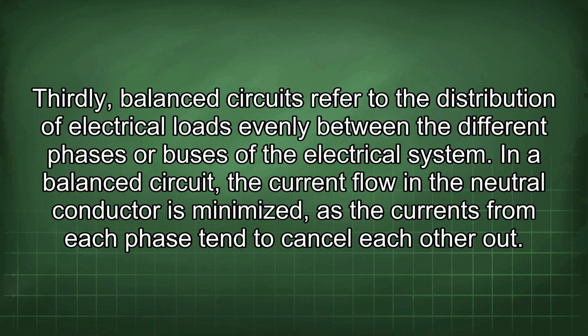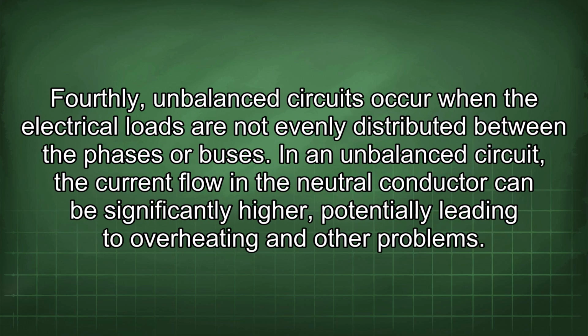Thirdly, balanced circuits refer to the distribution of electrical loads evenly between the different phases or buses of the electrical system. In a balanced circuit, the current flow in the neutral conductor is minimized, as the currents from each phase tend to cancel each other out. Fourthly, unbalanced circuits occur when the electrical loads are not evenly distributed between the phases or buses. In an unbalanced circuit, the current flow in the neutral conductor can be significantly higher, potentially leading to overheating and other problems.